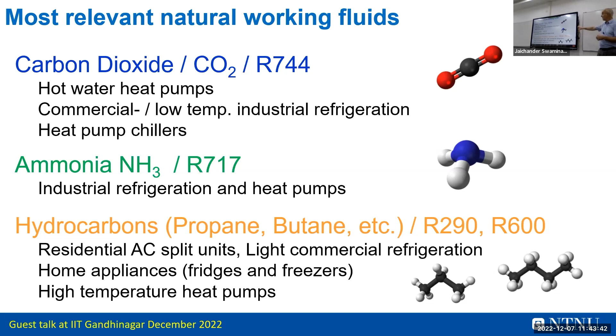So what can we do? We can upgrade heat from the chiller, 40 degrees, we can upgrade it to 120, 150. And there we can use hydrocarbons with different properties, tune these systems, and then you can provide, with a relatively good COP, these high temperature lifts and produce steam, for example. So it's also possible. So we have the toolbox, we have the components. So let's have a look at what we can do.